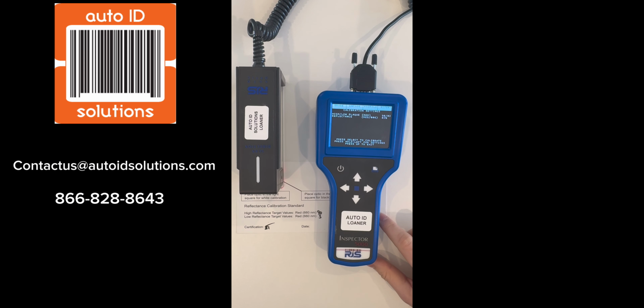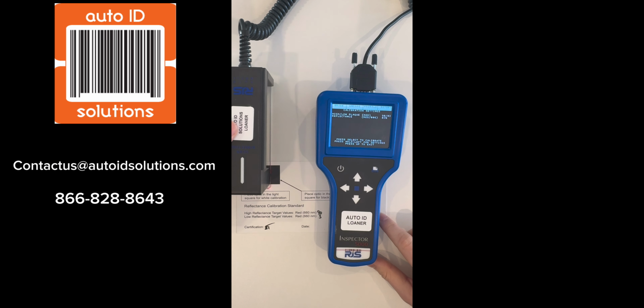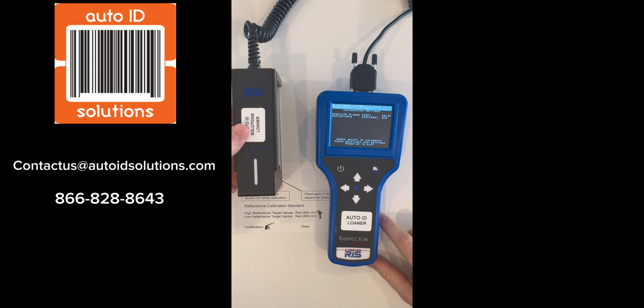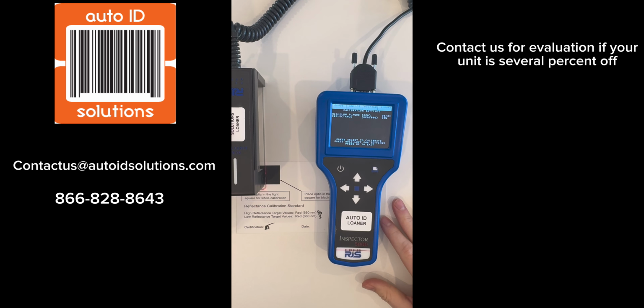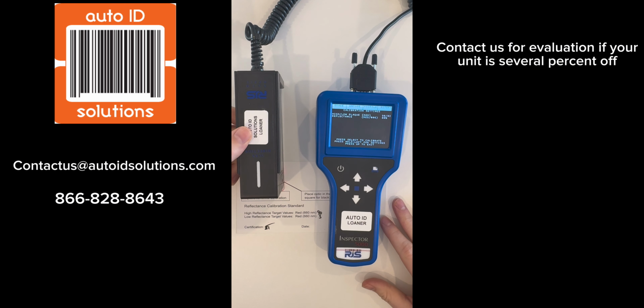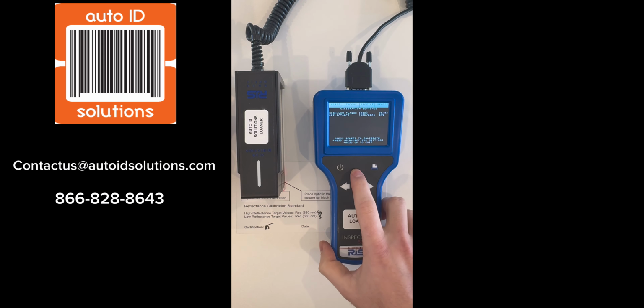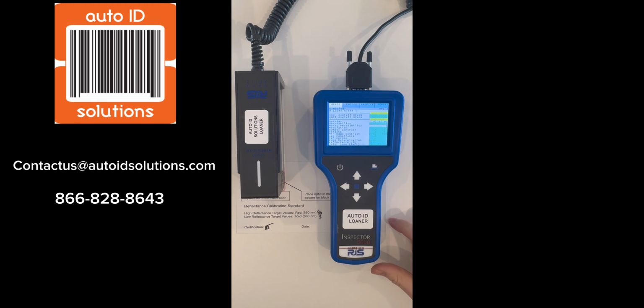To test that your unit is reading the reflectance accurately, you can move the Auto Optic head over each square when in this screen and see what reflectance value it is reading. It should be within a few percent of the value shown on your calibration card. Press up to exit the calibration screen.